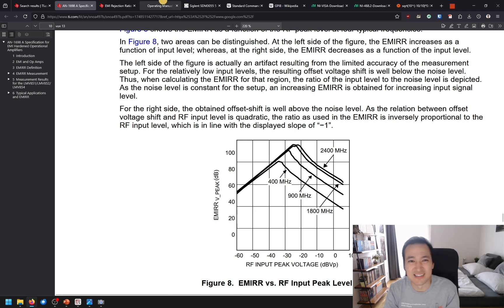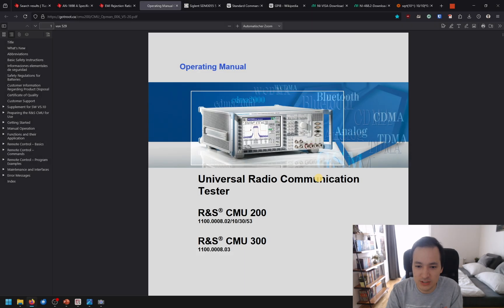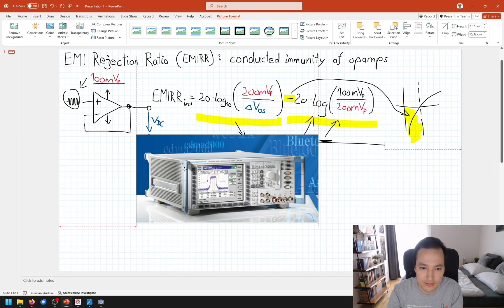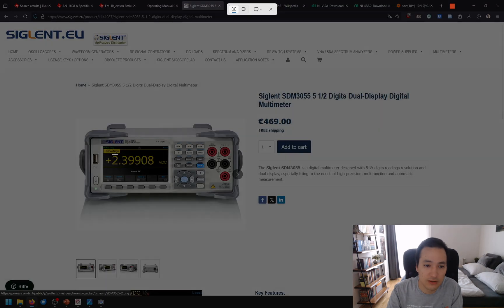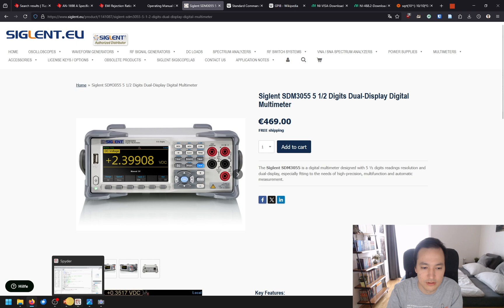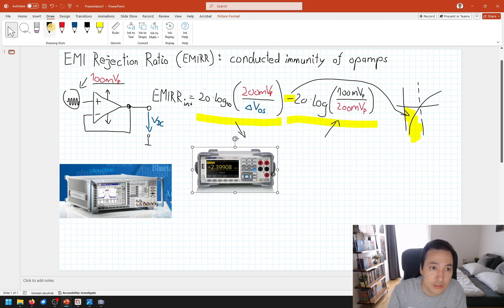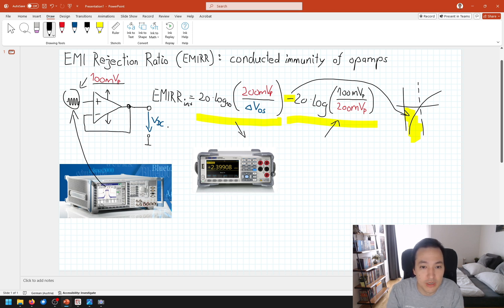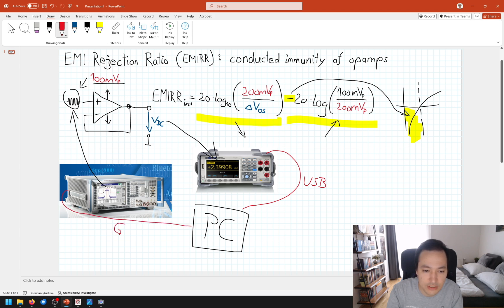For our lab exercise, I have prepared two measurement instruments. First, here we have our CMU200. And second, I have here this Siglent voltmeter. We will use the CMU200 to generate our RF signal, and we will use our Siglent voltmeter to capture the DC voltage. Then we will use our PC for automation. We can connect our voltmeter with a USB cable to our PC, and we connect the CMU200 with a GPIB cable.